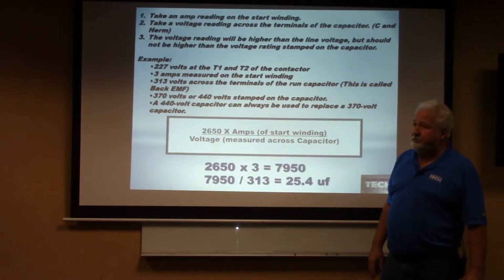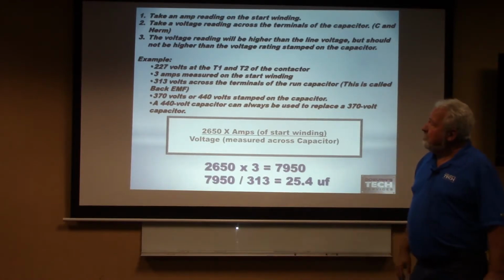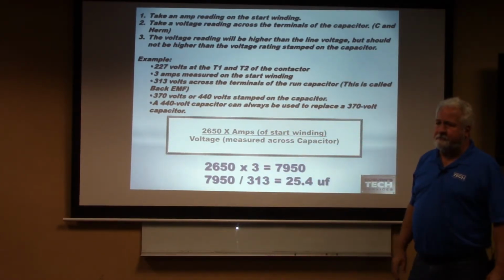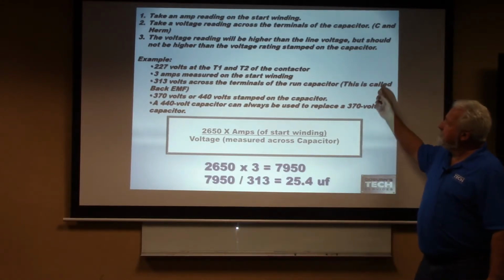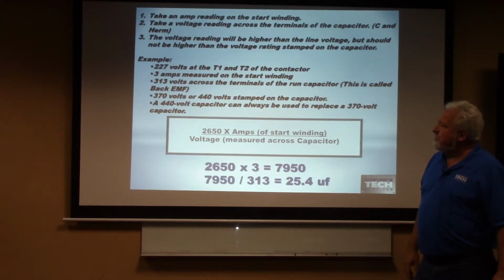All right, so let's do that. What we're going to do, take the amp reading on the start winding. We're going to take the voltage readings across the terminals of the C and Herm on our capacitor. The voltage reading is going to be higher than line voltage. Is that right? Because that's that back EMF that we're measuring right there. So example, if I had 227 volts on my T1 and my T2 of my contactor, I had 3 amps measured on the start winding, I might see 313 volts across the terminals of the run capacitor, because that's generated voltage going back there. That's called that back EMF. 370 or 440 on the capacitor. A 440 capacitor can always be used to replace a 370 because that's just the storage capability of that capacitor.